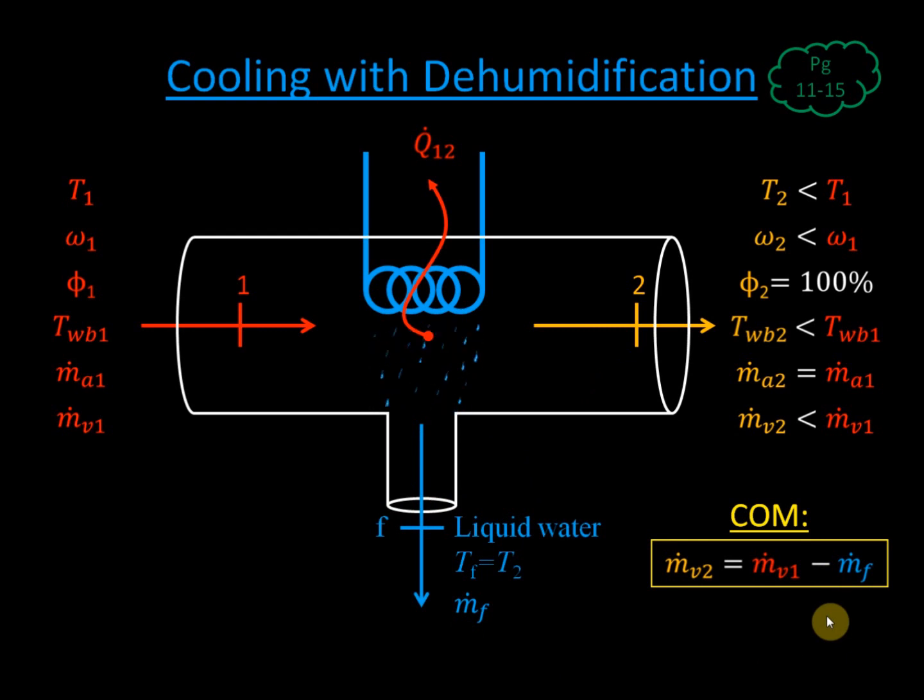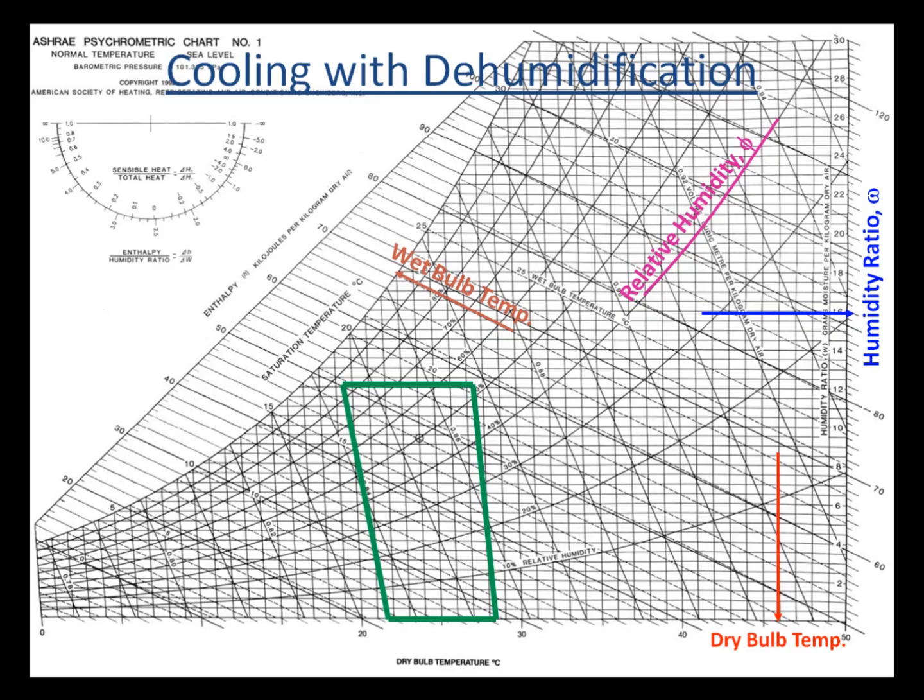You want to dehumidify the air, like a dehumidifier you would put in your basement, for example, to keep moisture from building up if you live in a damp environment that would cause mold, etc. Let's look at this on a psychrometric chart, and we're going to talk about the relationship between humidity ratio and relative humidity, and how that condensate forms and why you have to be at 100% saturation. It's the only way to extract water from atmospheric air: to actually cool it.